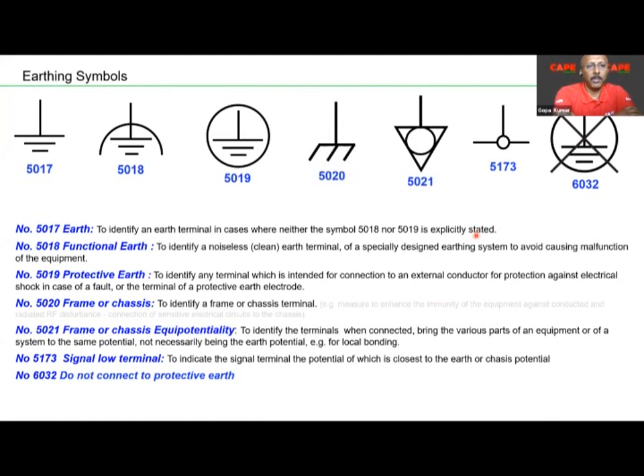For this purpose, the IEC and all the world standards define earthing into various types, and various numbers are allocated to each earthing. This is followed not only by IEC; it is the same in ISO, ITU, and all the standards. For example, 5017 is a generic symbol. 5018 is an earthing called a clean earth, or the new word, functional earth. For functioning of an electronic appliance, the appliance, the panel board, or the PLC will have an earth terminal, which is marked with 5018.